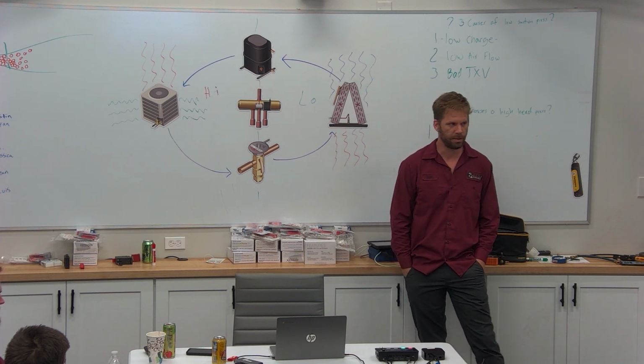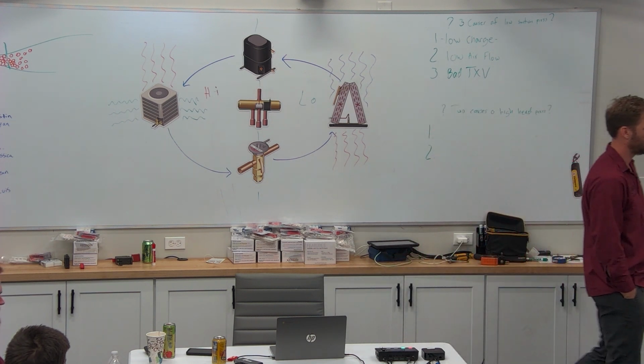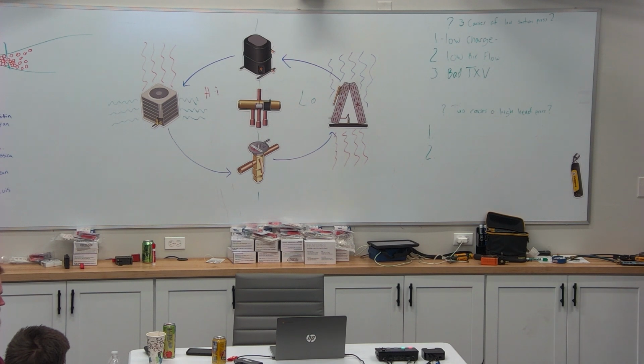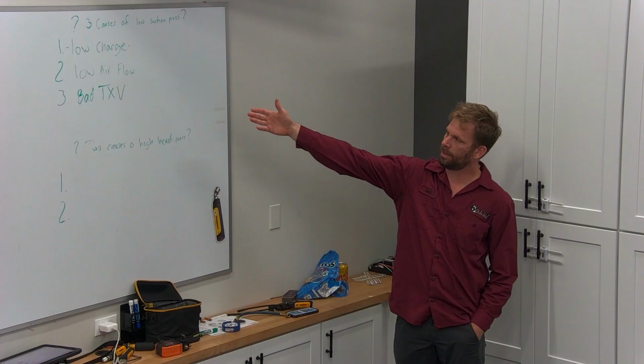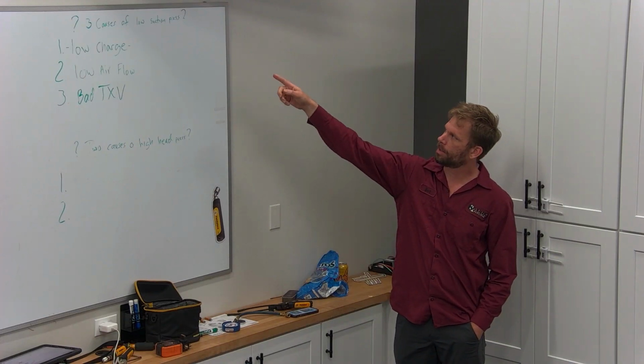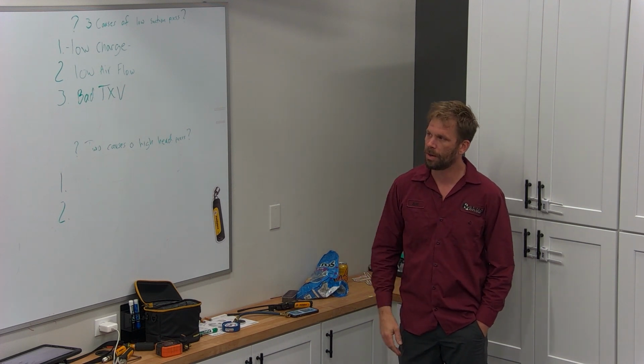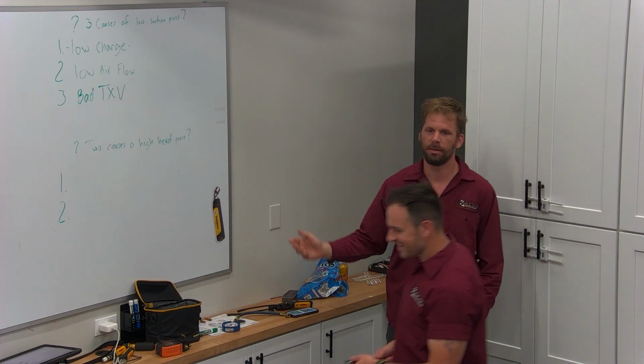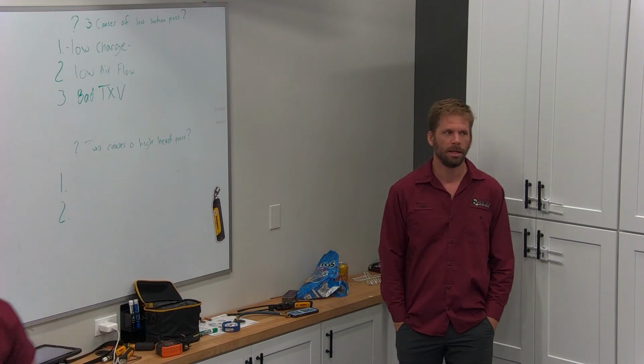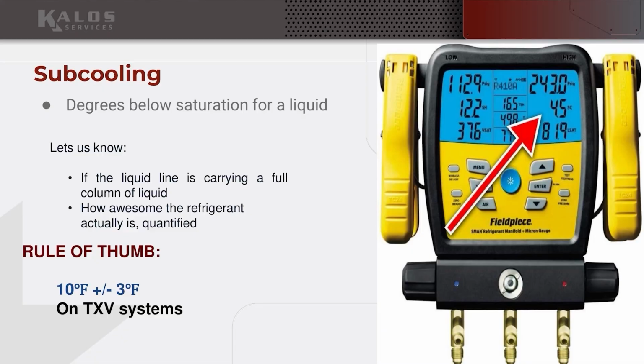by taking more measurements of the system? Whether it was low charge or a bad TXV that's restricting it and causing our low suction, now we need to take more measurements of the system, using our 5 pillars. Okay, subcool. What will subcool tell us? That you have enough refrigerant. If your subcool's good, you've got enough refrigerant, it's just your TXV.